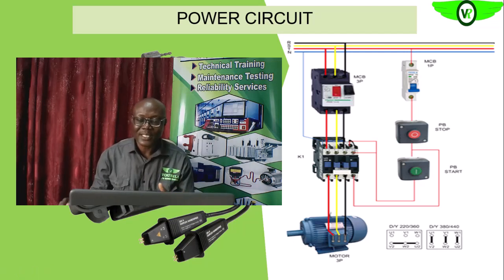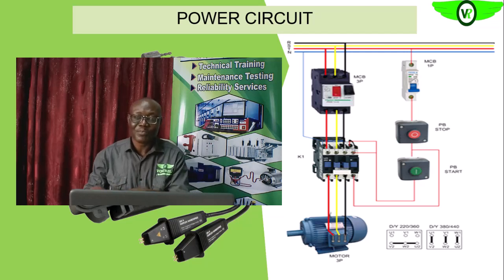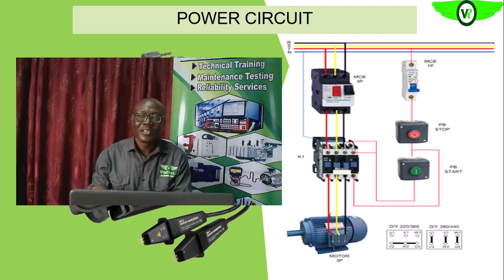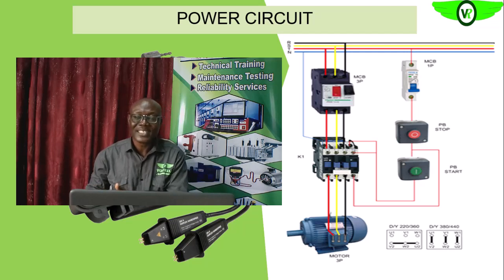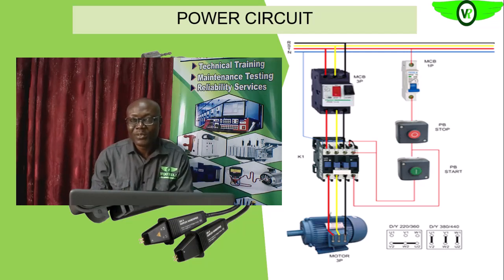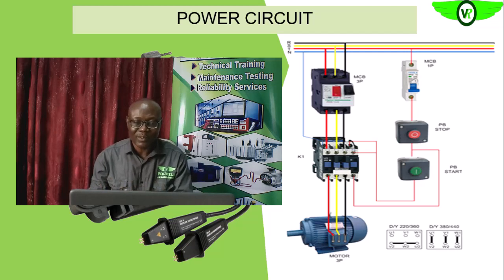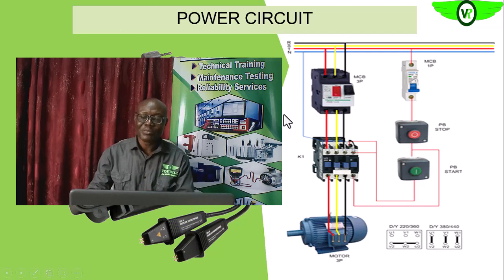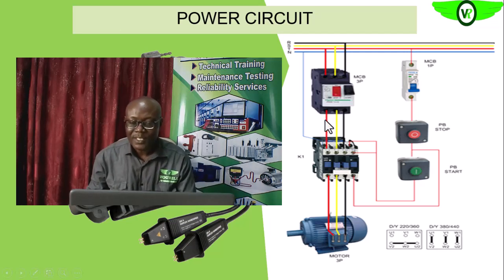Remember, we also look at the average, subtract each of these resistances from the average, the maximum deviation, as we said earlier, when we are looking at the voltage unbalance, we divide it with this average, okay, to give us the percentage unbalance. Are we getting it?